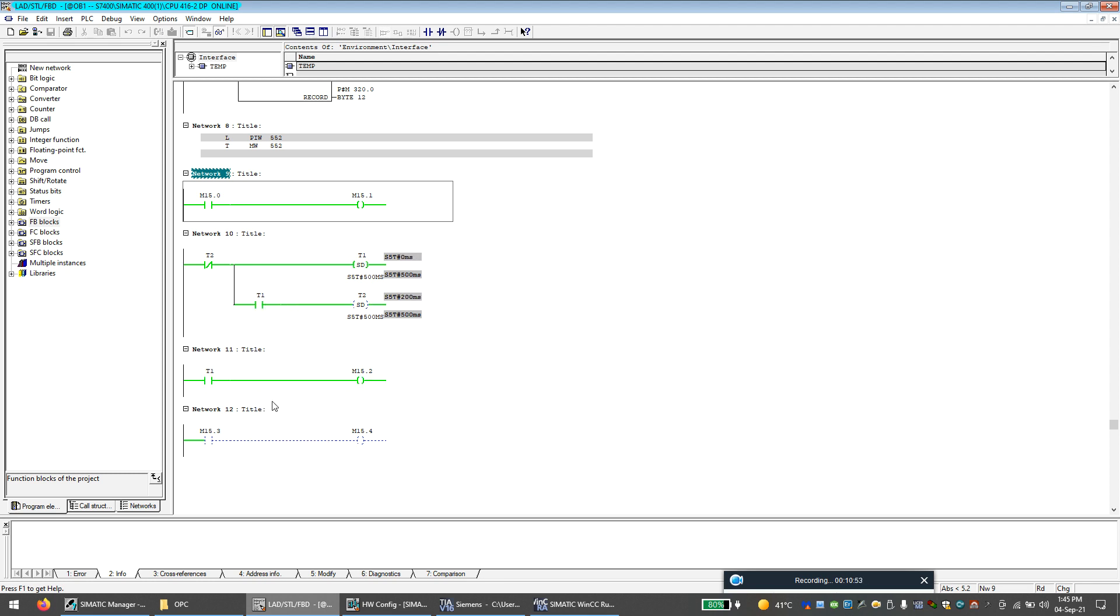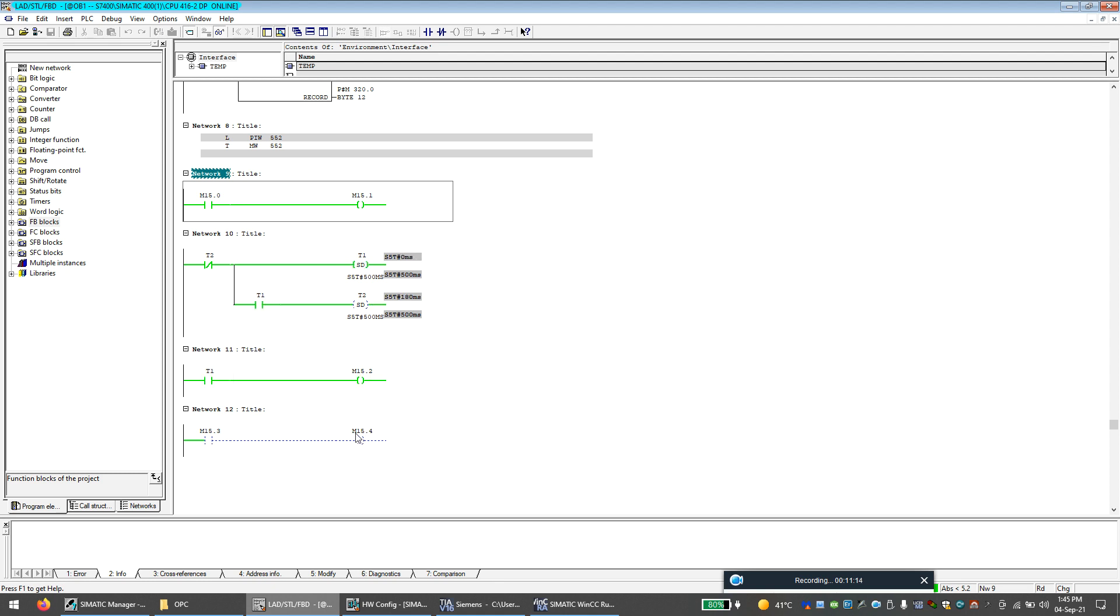Now what we can do is, for example, let's say we want to make sure the SCADA is communicating with the PLC. So what I will do is I will use this bit M15.2. I will take this bit to the WinCC SCADA system and I will generate a bit called M15.3, which will activate this bit. I will connect this bit to 15.3 in the SCADA system and I will use this bit to make sure the SCADA is communicating properly.